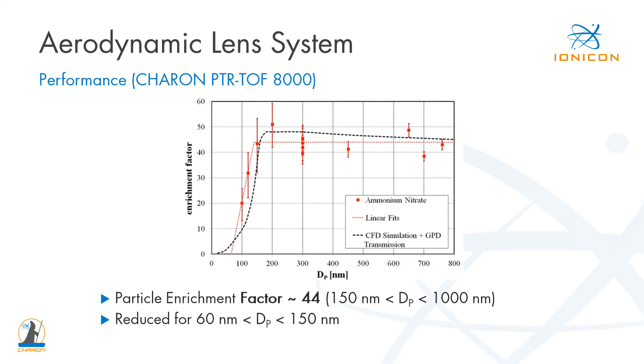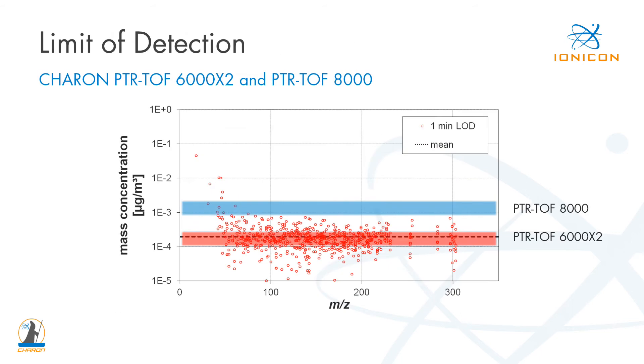Now let's have a look at the particle enrichment capability of the aerodynamic lens system. The figure shows the particle diameter on the x-axis and the absolute particle enrichment factor on the y-axis. In red, measured enrichments for ammonium nitrate particles are plotted, and in black I have added our CFD simulations. CHARON offers a very stable particle enrichment factor in the size range between 150 and 1000 nanometers. Coupled to a PTR-TOF 8000 instrument, this factor is in the range of 40. For sizes smaller than 150 nanometers, particles are not properly collimated to the center of the aerodynamic lens system, so the response is reduced. With these properties, CHARON's size range is very much comparable to the one of TOF-AMS instruments.